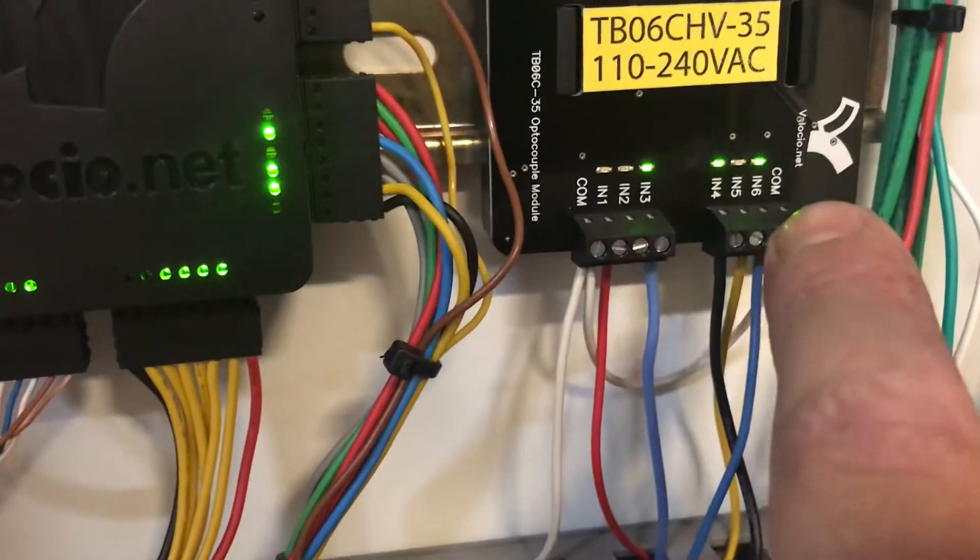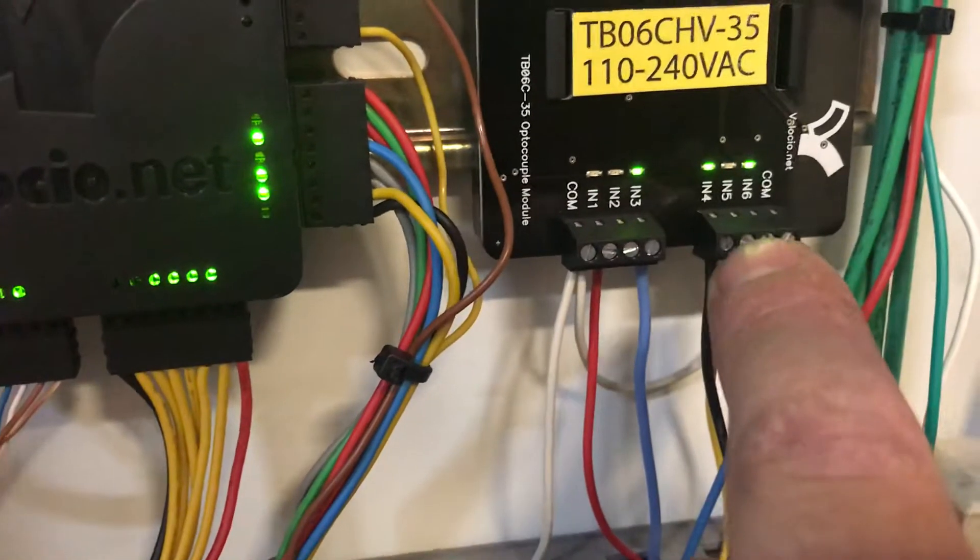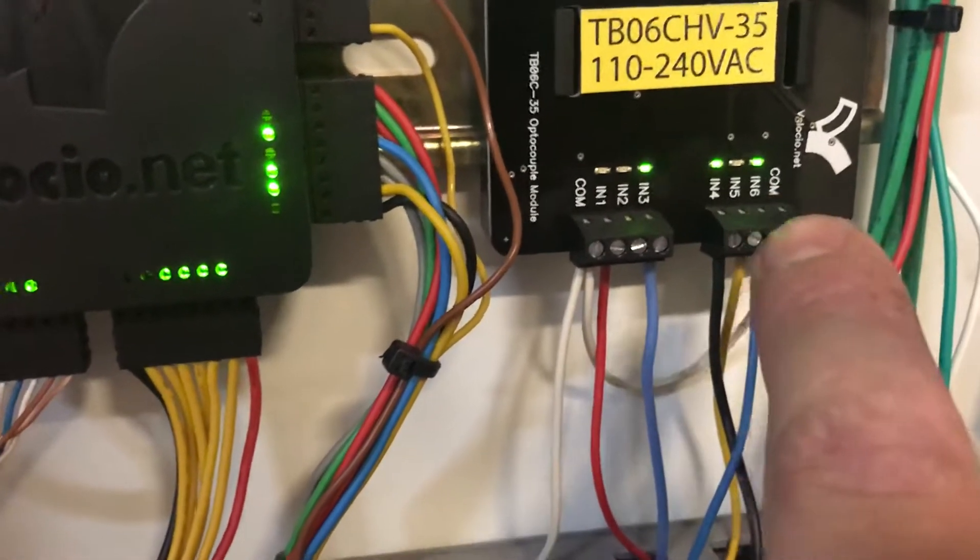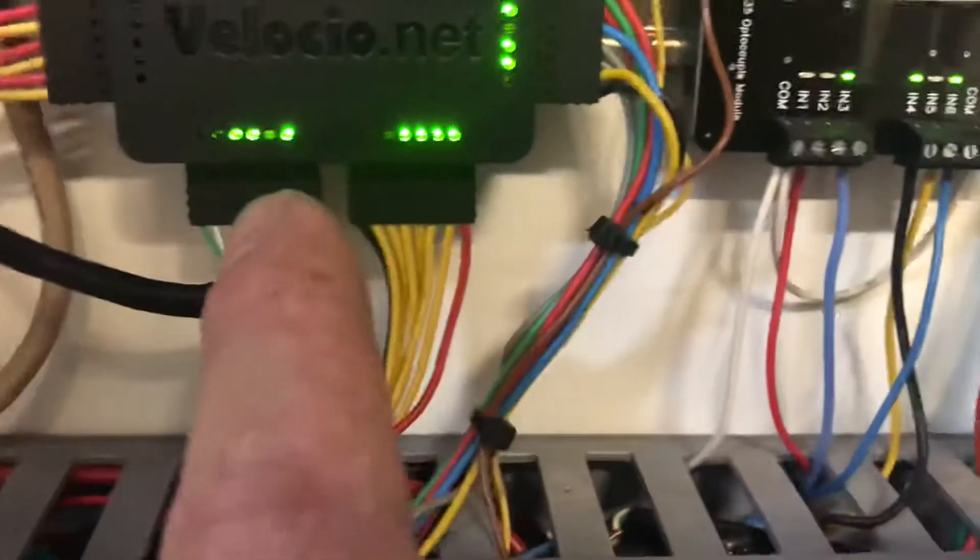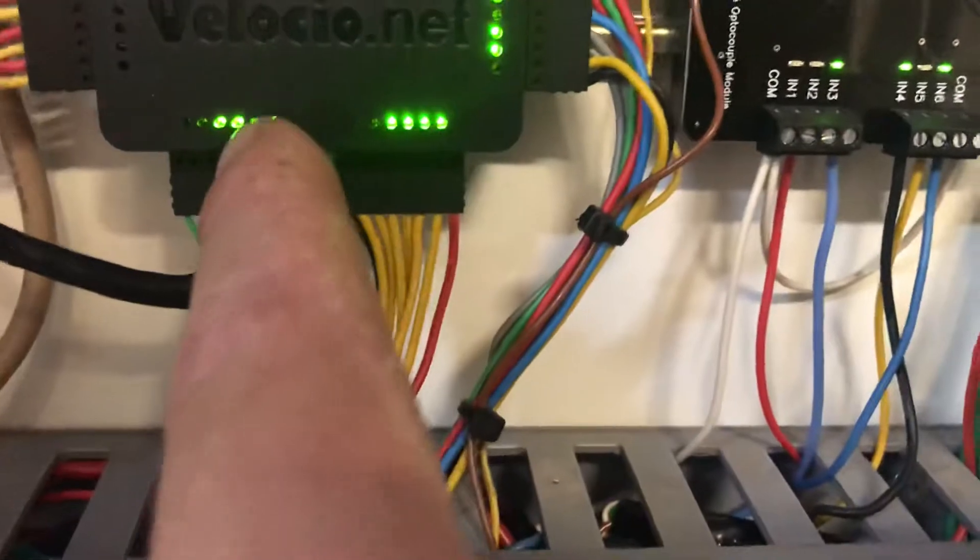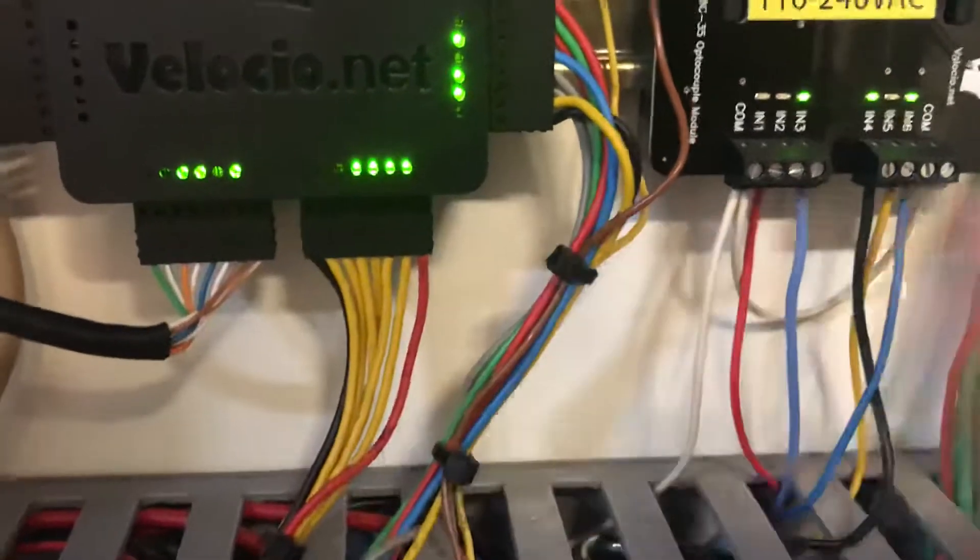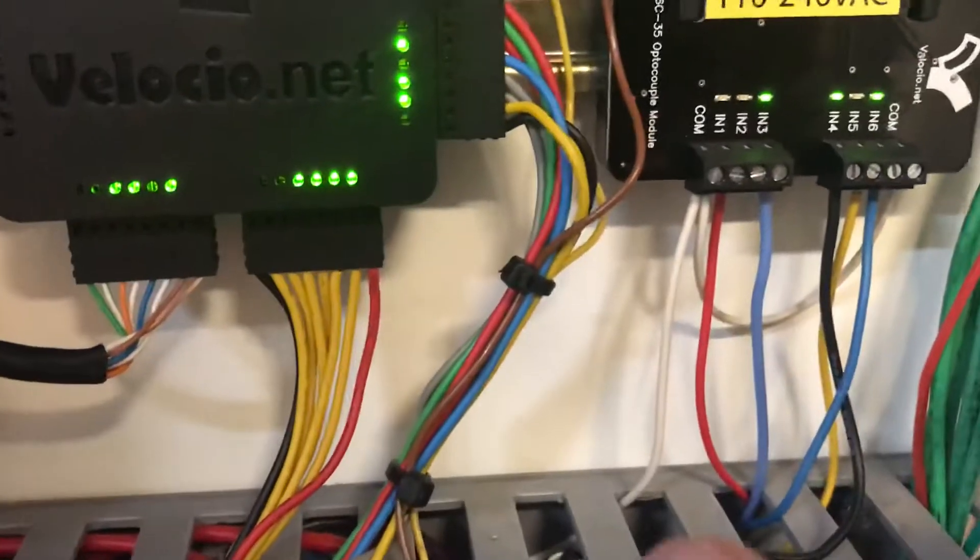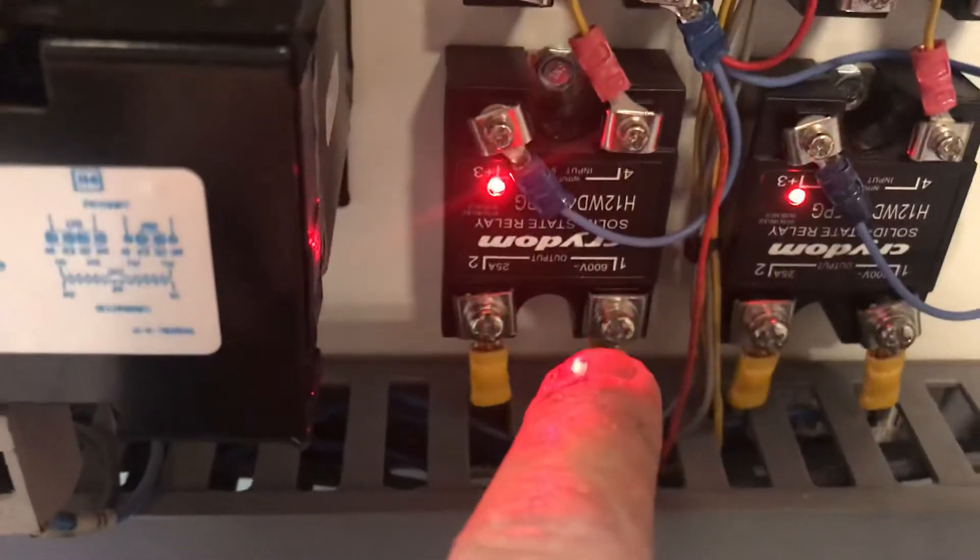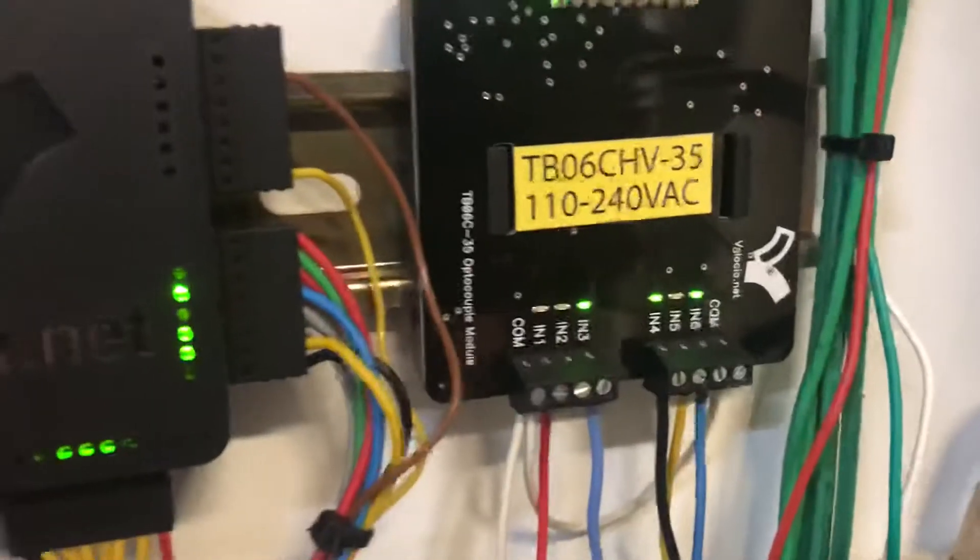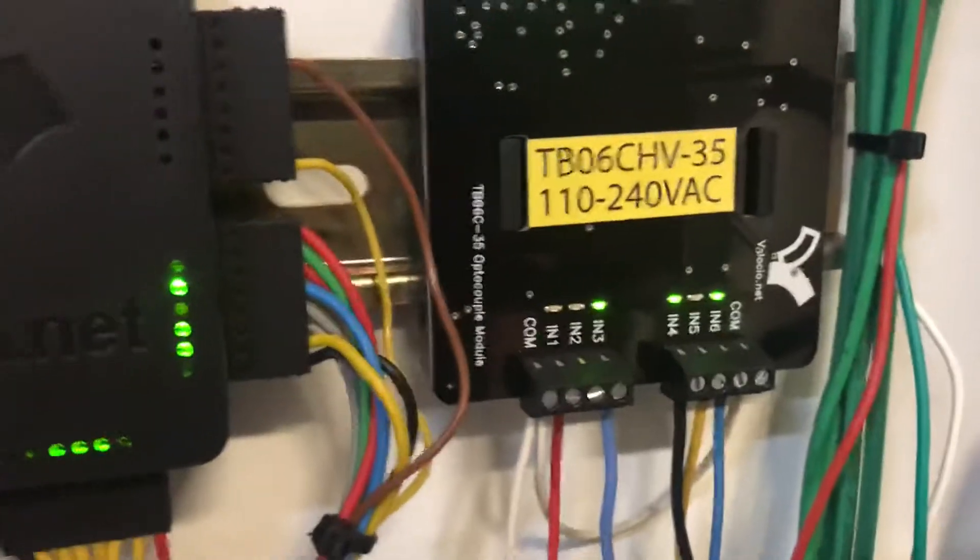It is on and it's showing that it's on, and the PLC LED is agreeing with it. It's working correctly. These two relays are being told to be on because it's told that there's an input and the burner is lit.